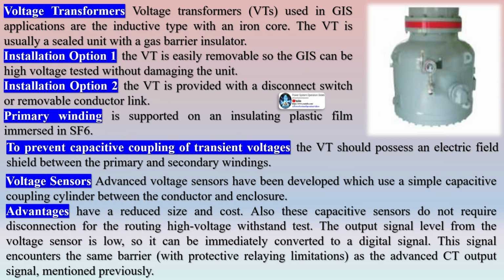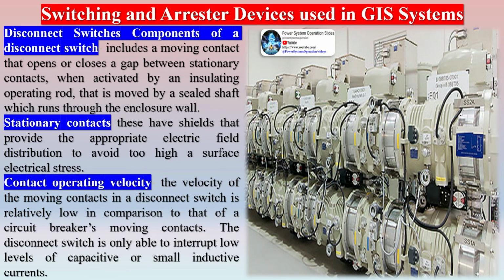Voltage transformers. VTs used in GIS applications are the inductive type with an iron core. The VT is usually a sealed unit with a gas barrier insulator. The VT is easily removable, so the GIS can be high voltage tested without damaging the unit. Installation option 2: the VT is provided with a disconnect switch or removable conductor link. Primary winding is supported on an insulating plastic film immersed in SF6.